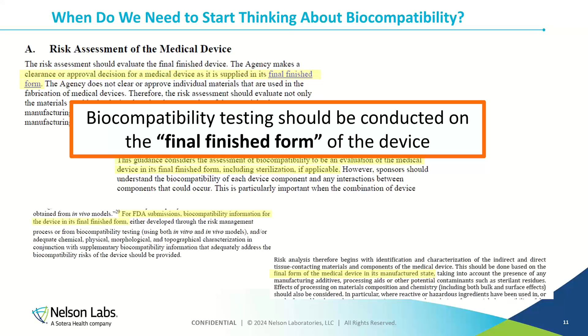Now, let's go back to when we need to start to think about biocompatibility, because that's a really important question here. When we look at the FDA guidance documents, and also ISO 10993-1, they all say that biocompatibility evaluation and testing should be conducted on the final finished form of the device. That's always what we hear: final finished device. Every time I talk to the FDA, they say, we don't clear any materials. We only think about the final finished device, right? So that echoes in my mind every single day.